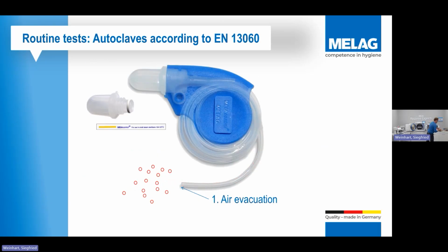So helix device, this is designed to emulate an overextended lumen instrument. So we have 1.5 meters of tubing inside of here, okay? Holes on both ends, hole on one end, links up to the little cap at the top. We then have a class 5 indicator that goes in the top, okay? And that goes in. These are only required for vacuum autoclaves. So we pop it into the middle shelf on the unit, okay? Go onto the tray, close the door.